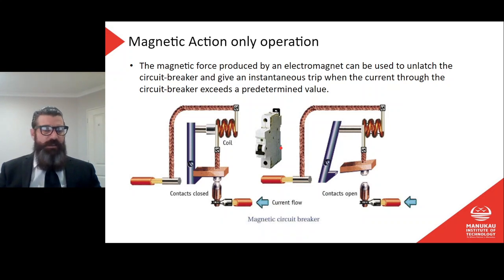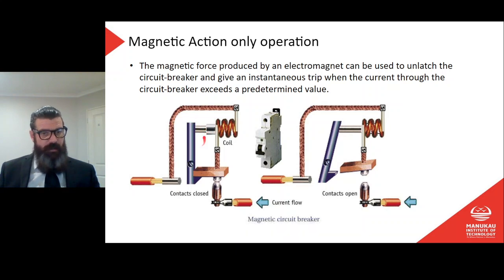Magnetic action. The magnetic force produced by an electromagnet can be used to unlatch the circuit breaker and give an instantaneous trip when the current through the circuit breaker exceeds a predetermined value. We go through here. Again, we've got our same latching mechanism there, same contacts, but now we have a little coil. So now we've got a little piston on the other side of the latching mechanism. That little coil there, when a very high current flows through, as I said before, it's going to move that piston, which will move the latching bar, which will no longer hold the contact. And remember, we've got a spring in here as well, which is actually going to push those contacts. So once that latching bar has moved, there's nothing holding the contacts closed. Spring pushes it, and we open the circuit once again.